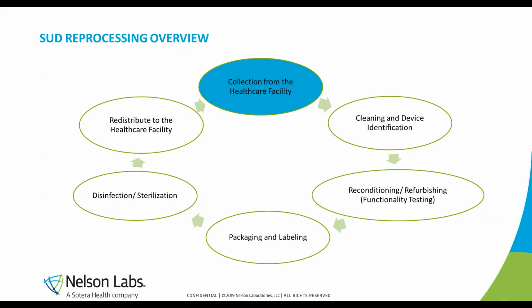Reprocessing and reusing single-use devices can save costs and reduce medical waste, but before medical devices can be reprocessed and reused, a third-party reprocessor must comply with the same requirements that apply to original equipment manufacturers or original device manufacturers, including submitting documentation for pre-market notification or approval as needed, registering reprocessing firms and listing all products, submitting adverse event reports, tracking devices whose failure could have serious outcomes, correcting or removing from the market unsafe devices, and meeting manufacturing and labeling requirements.